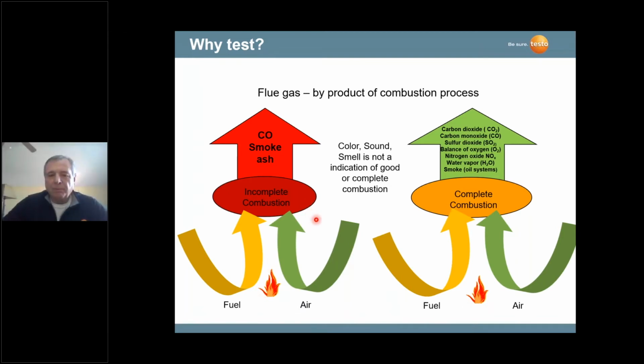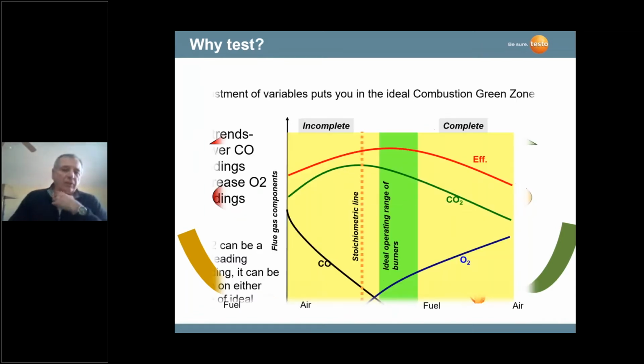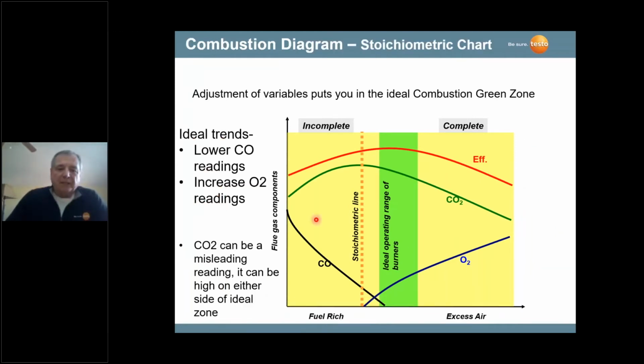We start producing high concentrations of carbon monoxide. In oil burners, we'll produce both CO and smoke. So we want to try to avoid, obviously, the incomplete side of the combustion process. We always want sufficient air to operate our burners. So let's go to this little graph here, and it may be a little complicated at first, but I'll take this step by step.